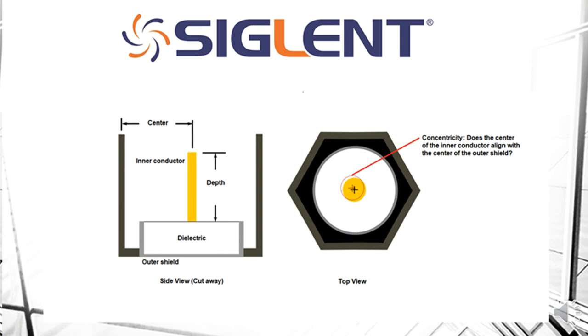We can also take a look at the center conductor height and concentricity of our connectors. There are special gauges available for that. And then there's the depth of dielectric and connector mating surfaces again also available with some special depth gauges. We're not going to go into detail of that but I did want to bring it up because it is very important.